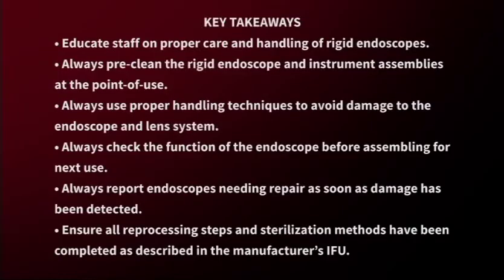The key points to use for effective care and handling of rigid scopes are: educate staff on proper care and handling of rigid endoscopes. Always pre-clean the rigid endoscope and instrument assemblies at the point of use. Always use proper handling techniques to avoid damage to the endoscope and lens system. Always check the function of the endoscope before assembling for next use. Always report endoscopes needing repair as soon as damage has been detected. And ensure all reprocessing steps and sterilization methods have been completed as described in the manufacturer's instructions for use manual.